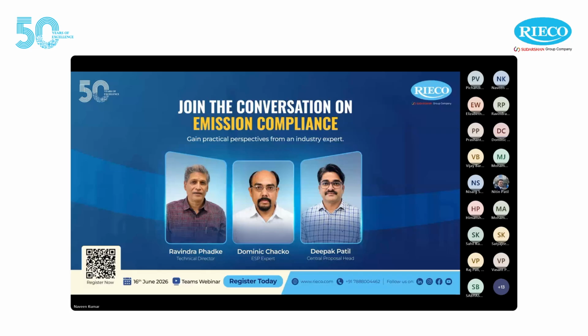And from an operations point of view, another point that I would like to mention is about the conveying equipment below the ESPs. At least in many of the power plants, where you don't find any other reason for a sudden increase in emission. Like I have seen many people find that an ESP, which has been working quite well, suddenly has developed a problem of emission. So in most of such cases, this problem really does not get traced to the ESP itself, but the problem is really with the auxiliary equipment like the conveying equipment.